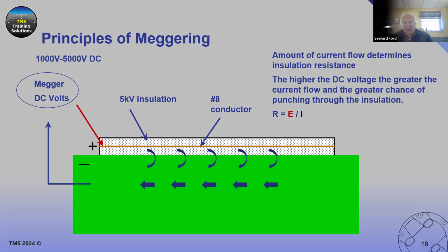Here are the principles: we put the megger DC volts on the conductor, anywhere between 500 and 1,000 volts. When automatic measuring first came out it was 500 volts, but now many automatic systems use higher voltages. So generally it's a 1,000 to 5,000 volt DC test voltage. You apply it to the conductor to see how much leakage there is from that insulation — whatever leaks flows through the ground back to the megger, and you read the resistance of the circuit in megohms.